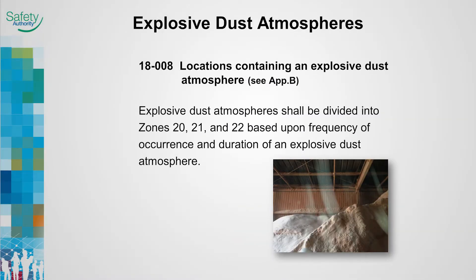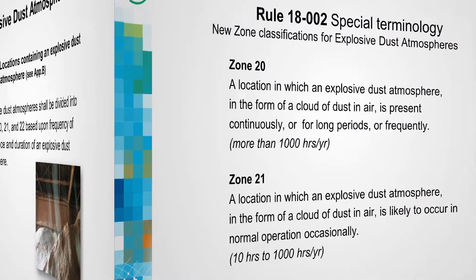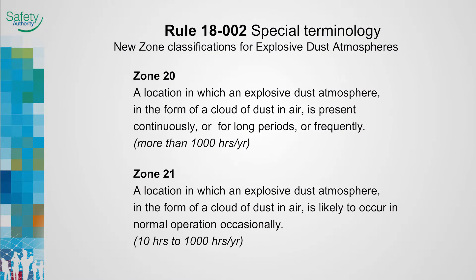Explosive dust atmospheres are categorized on the basis of how often the hazard occurs and the length of time the hazard exists. The classifications and associated timeframes are from the International Electrotechnical Commission Standards for Hazardous Area Classifications. Zone 20 is a location with the highest risk of explosion; if an explosive dust atmosphere is present more than 1,000 hours a year, it is a Zone 20 location. Zone 21 is a location with a lesser risk; if present from 10 to 1,000 hours a year, it is a Zone 21 location.